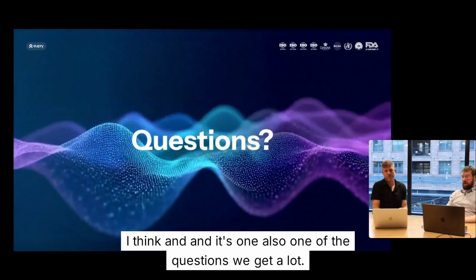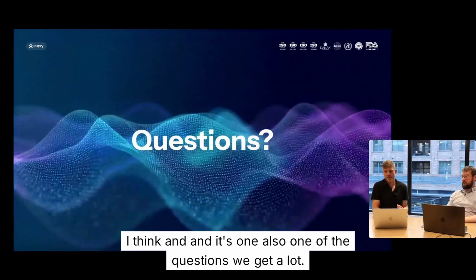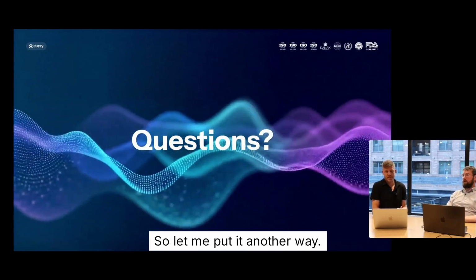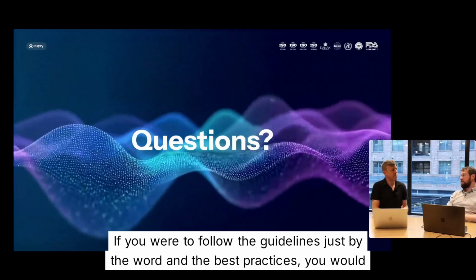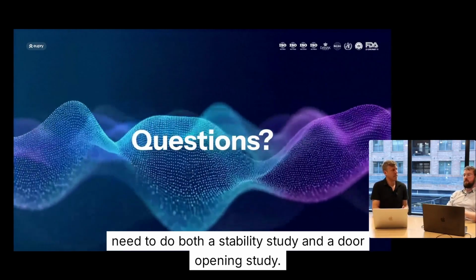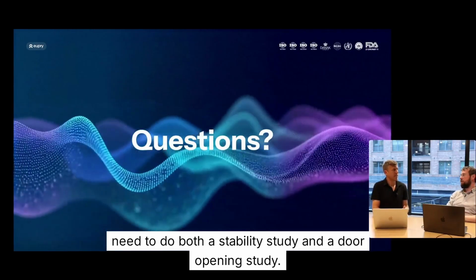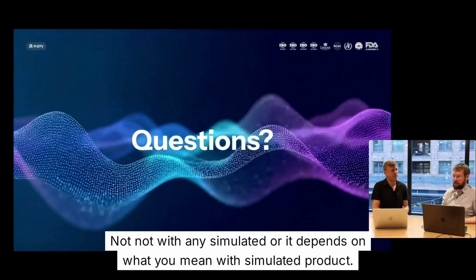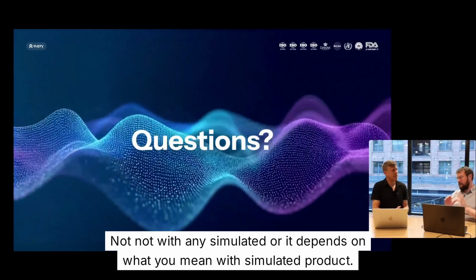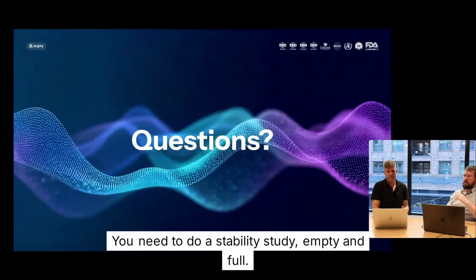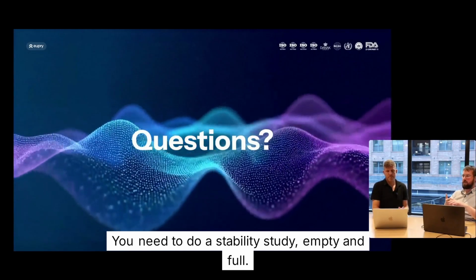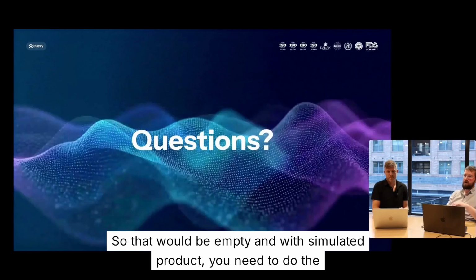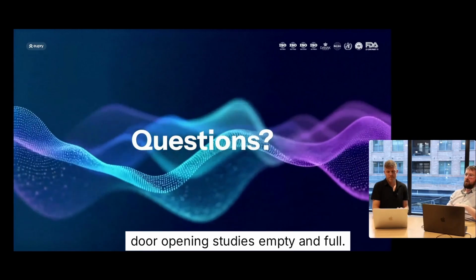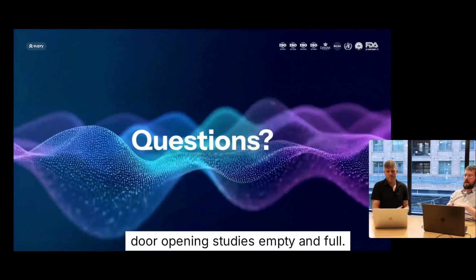First of all, it's also one of the questions we get a lot. So let me put it another way. If you were to follow the guidelines just by the word and the best practices, you would need to do both a stability study and a door opening study, and it depends on what you mean with simulated product. The guidelines are quite clear. You need to do a stability study, empty and full, so that would be empty and with simulated product. You need to do the door opening studies, empty and full.